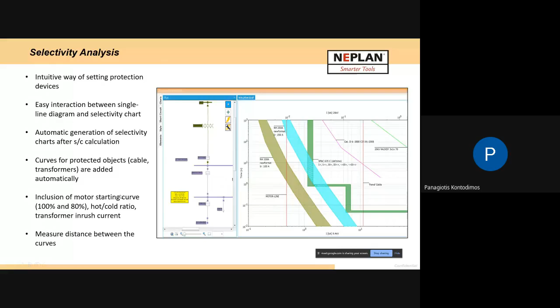Now for protection, as mentioned, we can make the selectivity analysis and the protection coordination. We can see the selectivity chart. For example, in this part we see a fuse, a circuit breaker, an overcurrent relay, and all the protection equipment, and we can make the settings, the protection settings, directly on the selectivity chart to ensure that we have selectivity in our network.